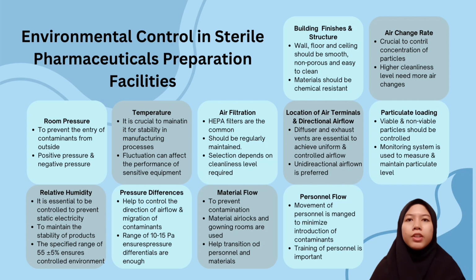First, building finish and structure. Its design should minimize particle generation. Wall, floor, and ceiling should be smooth, non-porous, and easy to clean. Then, air filtration. It is a critical aspect of clean room design. HEPA filters are commonly used to remove particles of various sizes from the air. Next, air change rate. It is the number of times the entire volume of air within a clean room is replaced per hour, with higher cleanliness levels requiring more frequent air changes.